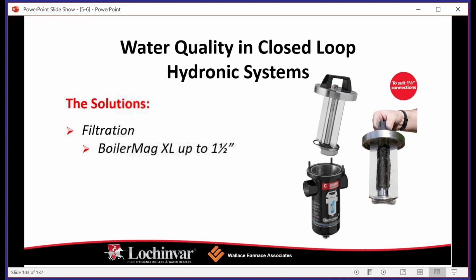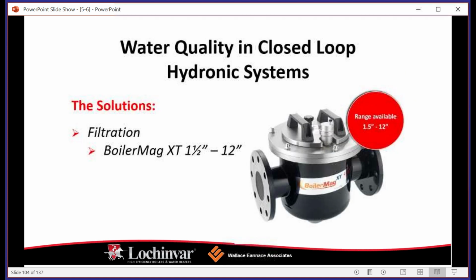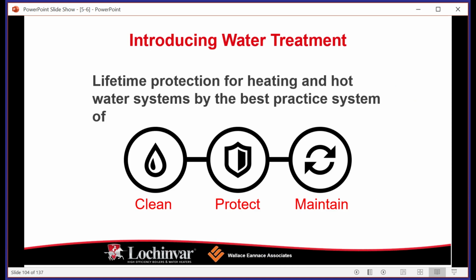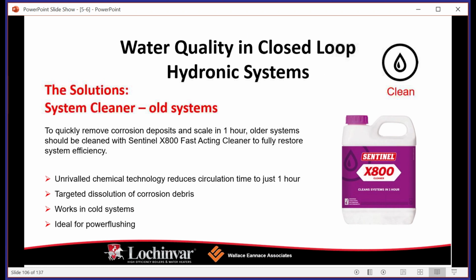Okay, so again, the circulator pump: when we talked about matching the boiler turndown, the boiler fire rate, to the speed of the pump, we achieve that by using an ECM pump, right? So an ECM pump, or electrically commutated motor, is going to vary the speed of the pump, and it's got a big old magnet right in the middle of it, right? So if you've ever pulled the boiler out and you've seen that black sludge, let's see if we have an example of it. That's called magnetite, okay?